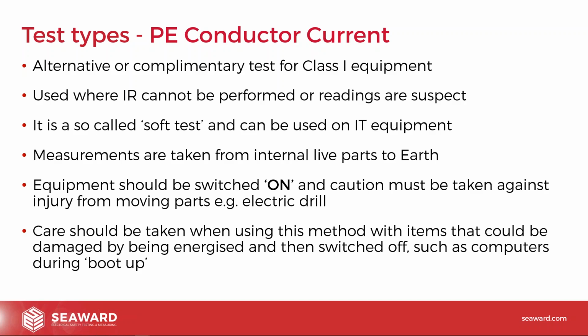Obviously, when you are carrying out this test, it is a mains powered test. So we are actually turning the equipment on. If it's a drill, it's going to spin round. If it's a grinder, it's going to spin round. If it's a kettle element, it's going to get red hot and glow. So just be careful with the precautions that you take. Obviously, with things like drills and grinders, you need to take out the drill bit, take out the cutting discs, all that sort of thing when you do the tests. If it's a kettle, obviously you've got to make sure there's water in it, otherwise the element is going to glow red hot. And take those precautions.